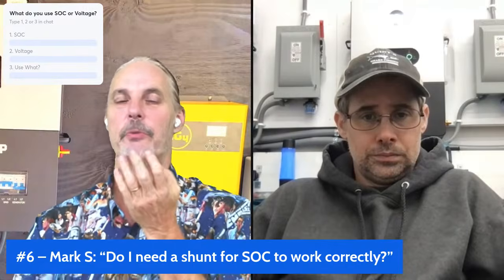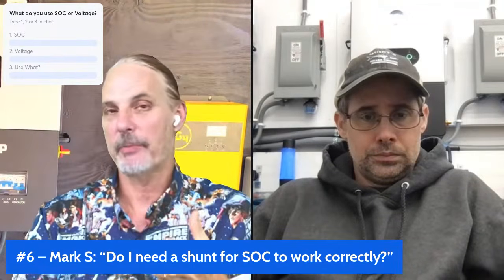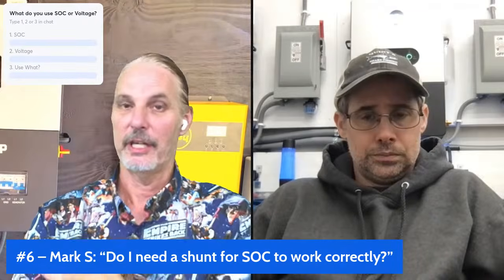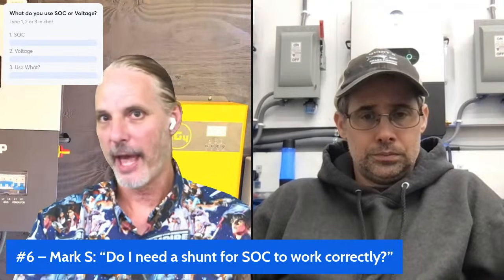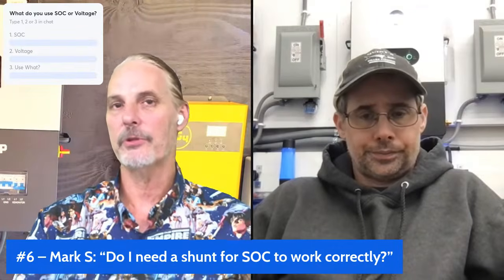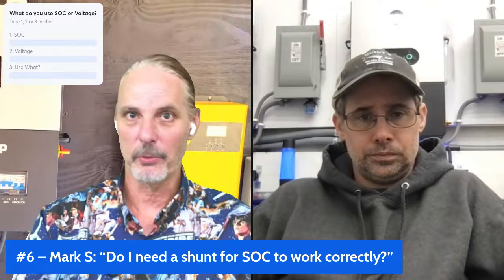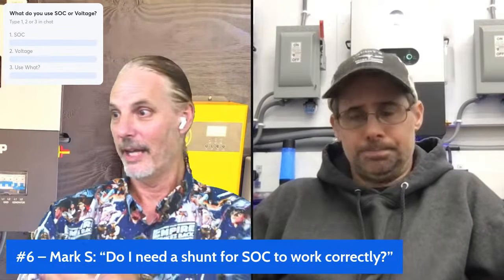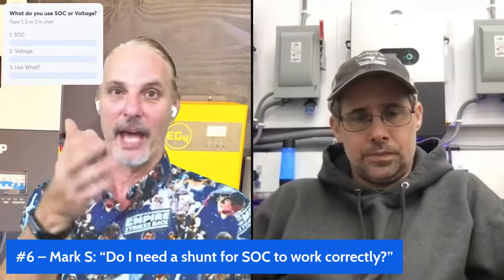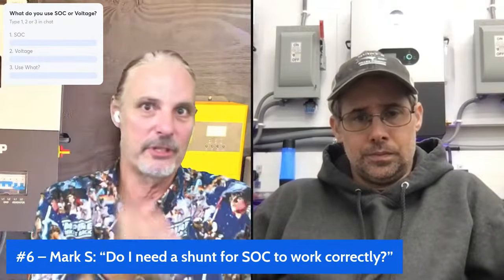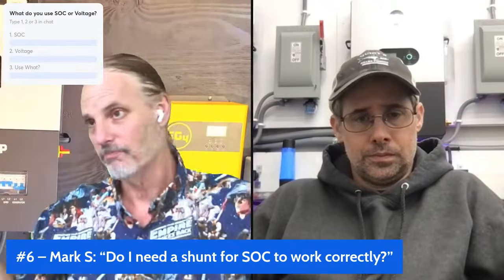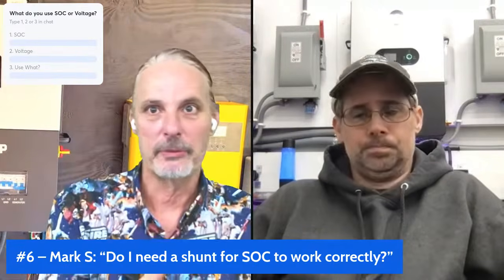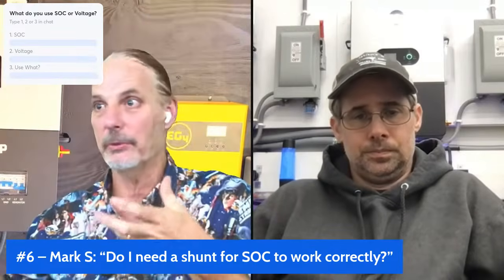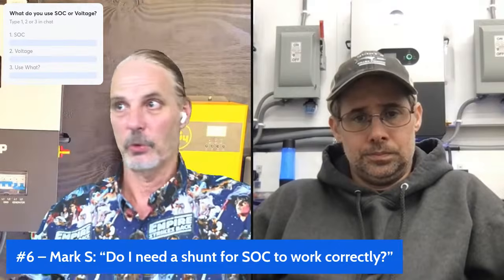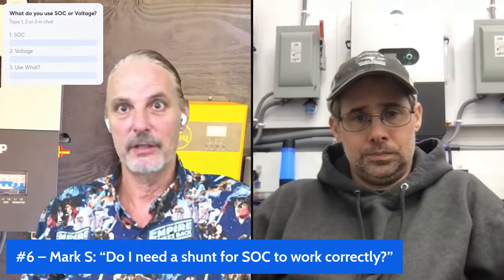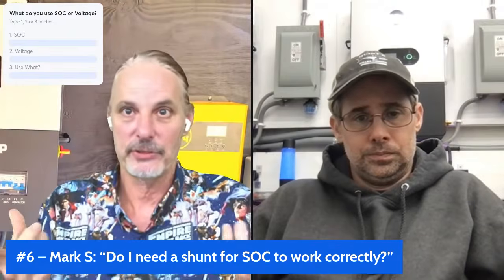The short answer is, if you want state of charge to be more accurate because you have multiple batteries, then chances are the answer is yes. But you have to make sure that whatever you're using for state of charge is compatible with whatever other equipment you're using it with. Yep. And the batteries either have to be compatible with each other, like if you have EG4 batteries, EG4 batteries and an EG4 inverter, easy. If you have two or three different battery types and some random inverter, or an inverter that doesn't have comms, then the only option you're going to have is some kind of shunt.